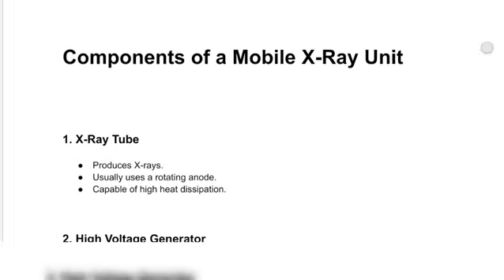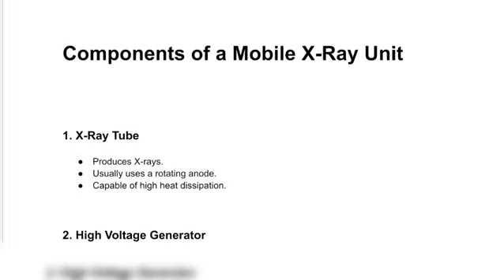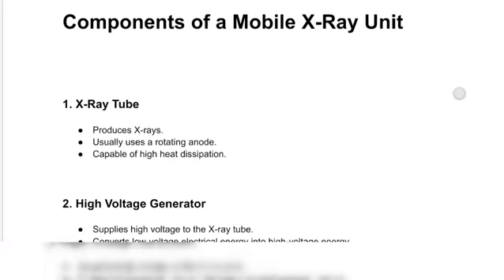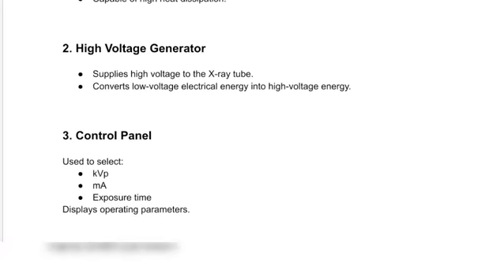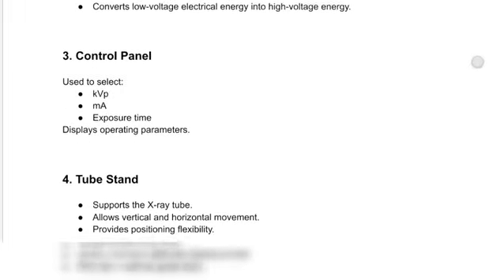Next is the components of a mobile X-ray unit. So what does a mobile X-ray unit consist of? First we are going to look at the X-ray tube. This X-ray tube helps us to produce the X-rays, and we mostly use a rotating anode X-ray tube, which is capable of higher heat dissipation. Next is the high voltage generator that supplies the higher voltage to the X-ray tube. It converts the low voltage electrical energy to high voltage energy.